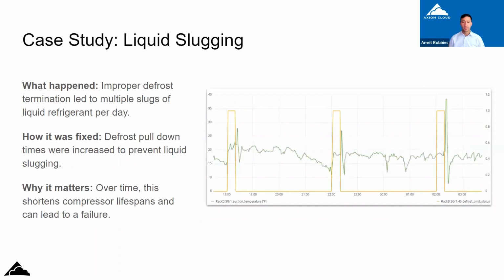So this is an example of using data to catch liquid slugging. Basically, there was an improper defrost termination that was set up in this particular grocery store for this particular case group. The pull down was not long enough. And so after each defrost cycle, there was a slug of liquid that would get sent back towards the suction header and was ultimately resulting in what we believe to be some droplets, at least, if not drops of liquid going into the compressor itself.